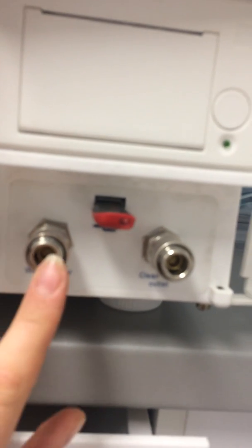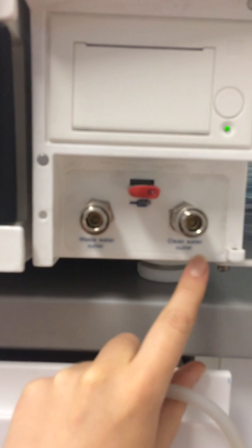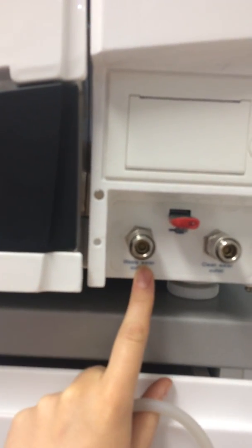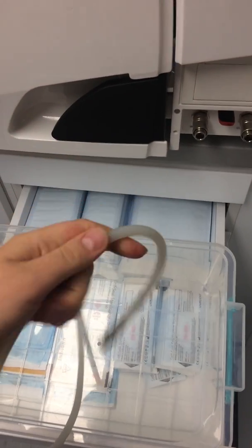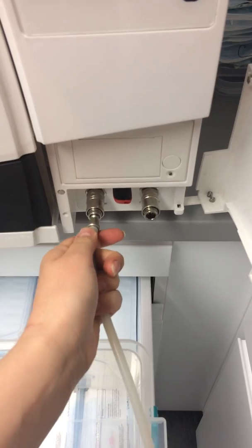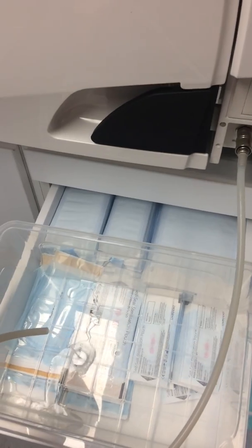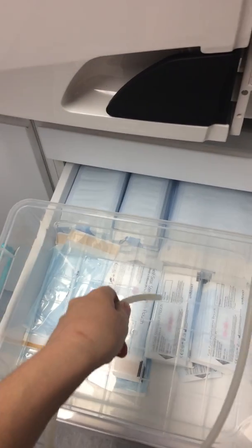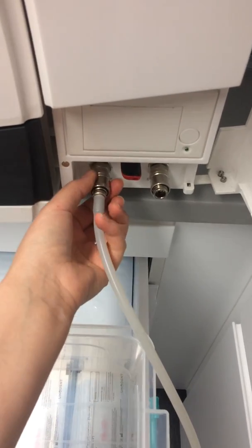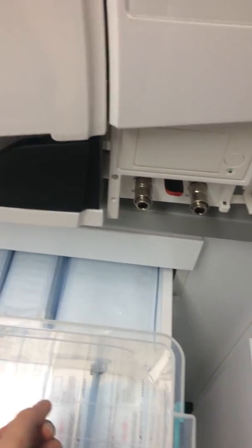If that doesn't work, then we can use another method. In front of the machine, you can see there are two connectors, two disposing units. One says wastewater output and the second clean water output. So don't mix them up. Use this one for the wastewater. The only thing we do is take something like a bucket, or I'll use this device. We put one side in the bucket and the second goes to the machine this way. And you can see the water is flowing out. The tank was emptied the last day, so it's empty. In order to take it out, you don't push it because you will break it. First you push back and then it comes off automatically. Okay, be careful with it.